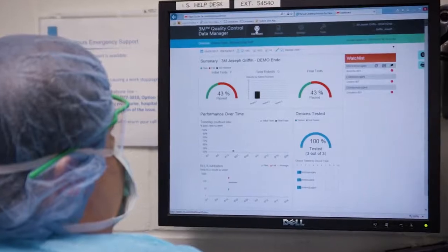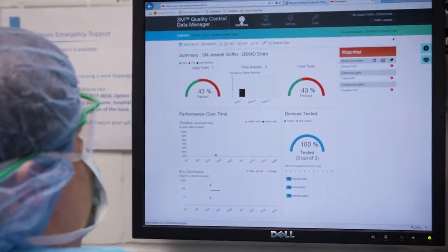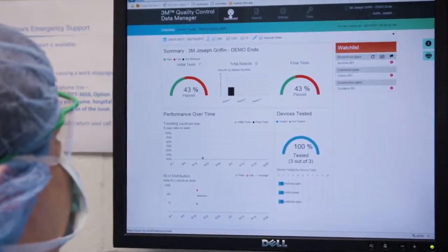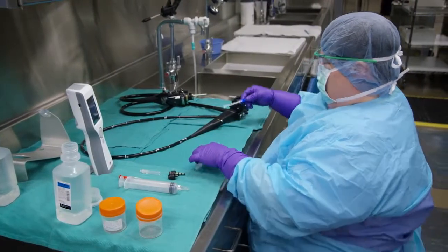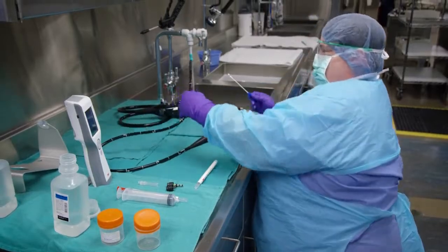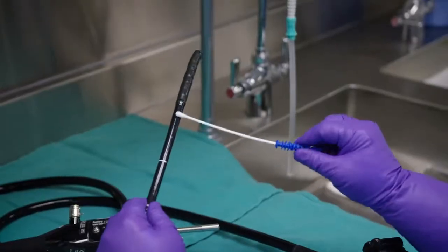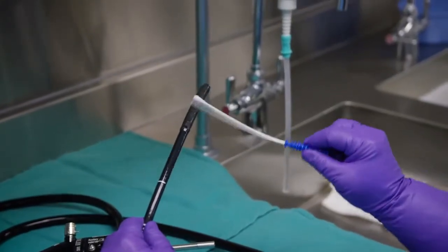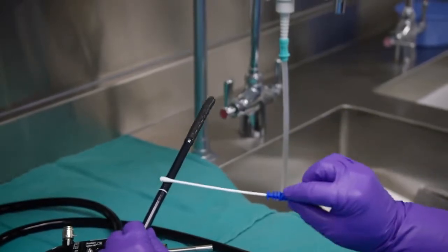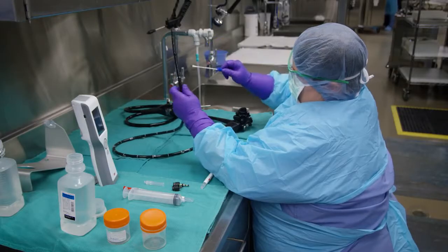Each cleaning verification test kit has its own benchmarks and thresholds that tell you whether or not there's still residual soil. So you have to read the instructions for use for each of those kits to make sure that you know exactly how to use it and how to interpret the findings. To perform an ATP cleaning verification test, swab the distal end surface or flush sterile water down channels and test the swabs or water for residue.